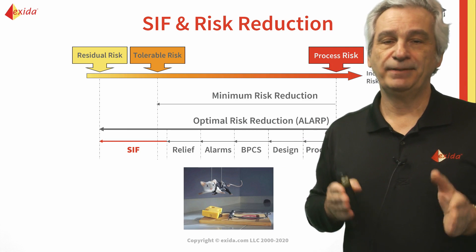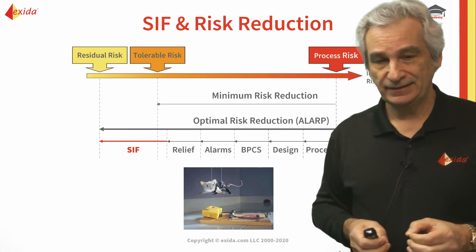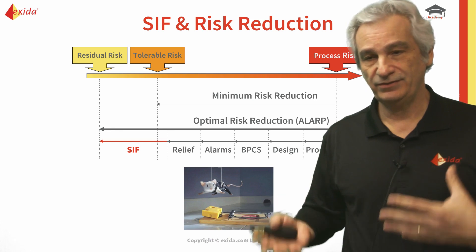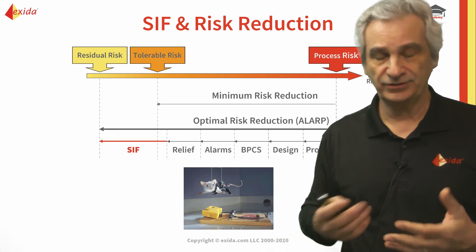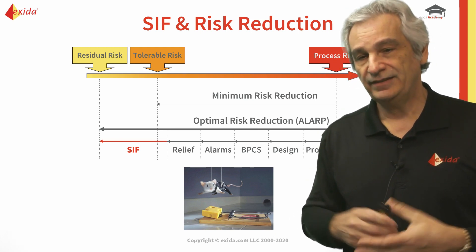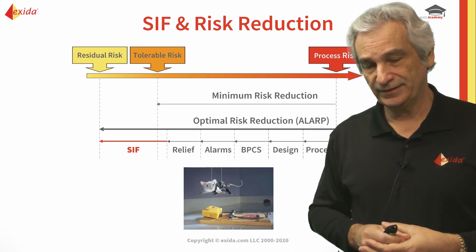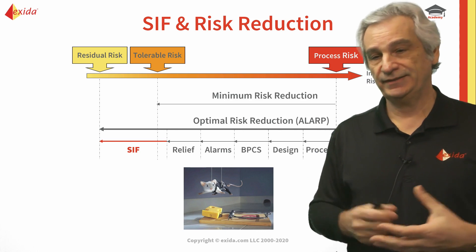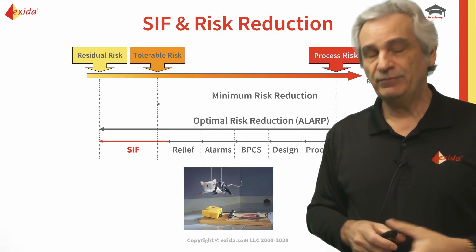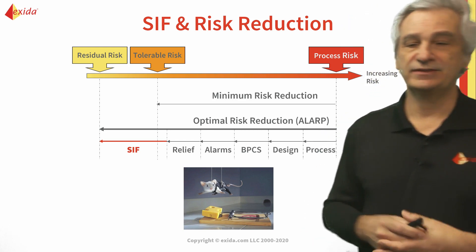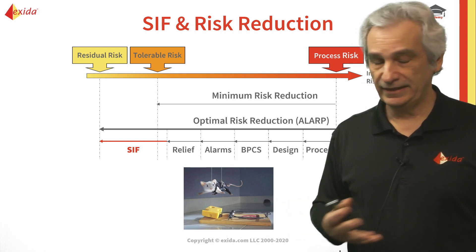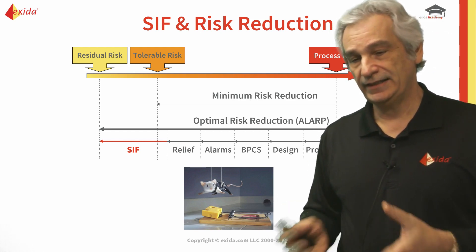Then of course we have our Basic Process Control System, our BPCS. This is our fundamental layer of protection for making sure that the process is within normal operating parameters in terms of temperature, pressure, etc. - this should keep everything running correctly. Then we might have some process alarms that enable operators to intervene to correct any deviation from normal parameters. Then we might have some form of mechanical relief for high pressure scenarios - that could be relief valves, rupture discs, etc. And then we'll have a Safety Instrumented Function potentially to get us to where we want to be.